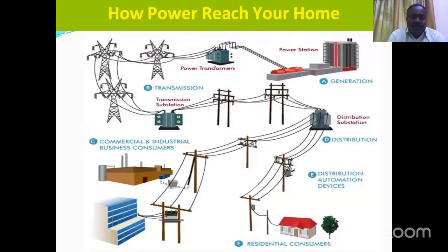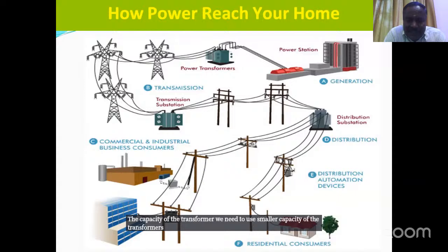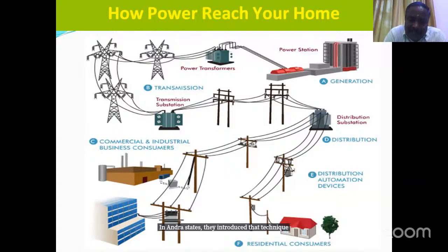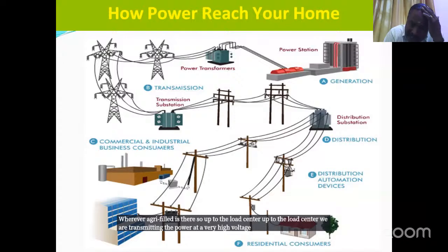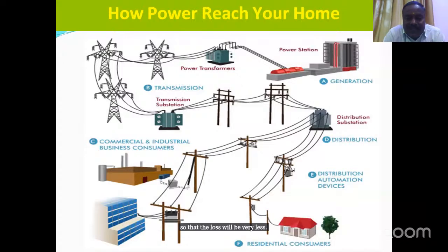The thing is, to reduce the transmission and distribution losses, we need to use smaller capacity transformers. In Andhra, they introduced the technique of using smaller capacity transformers, especially in the agri field. Wherever the agri field is, up to the load center we transmit the power at a very high voltage so that the loss will be very less. I square R loss: if I increases, loss will be high. If V increases, loss will be less. So we increase the voltage to a very high level, 11 kV or 22 kV, and transmit the power up to the house.